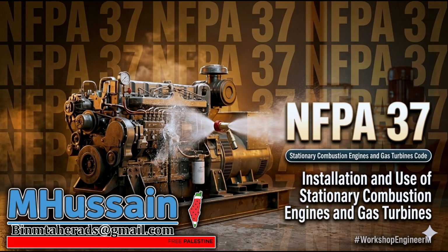Okay, so let's say we've got the site placed, the unit is bolted down, now it needs to breathe. Let's talk about the lungs of the beast. Ventilation is critical. An engine starved of air is a catastrophic hazard. So, looking at the physics, a typical 250 kilowatt diesel needs a wild amount of air. The numbers here are crazy. Yeah, a 250 kilowatt unit needs roughly 4,500 cubic feet per minute of cooling air.